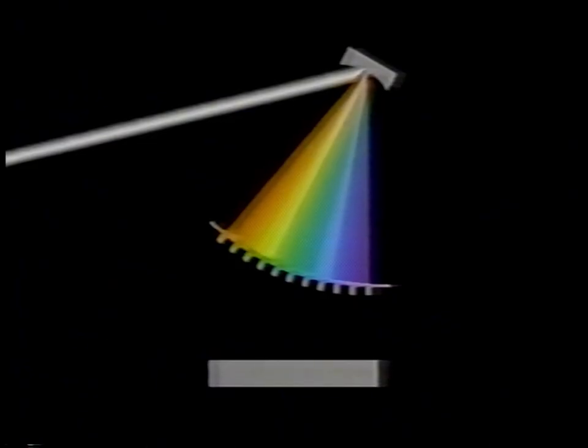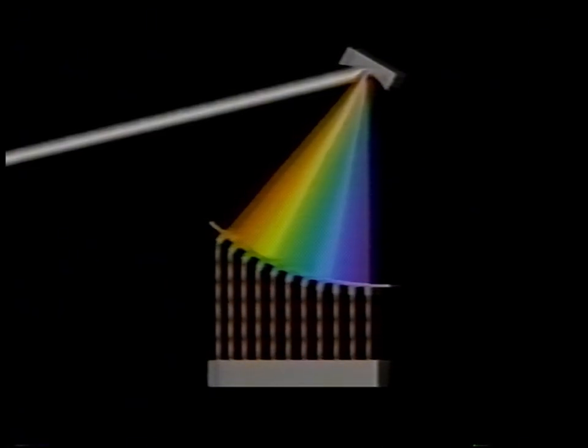A diffraction grating within the photometer diffuses the light into its component wavelengths. 12 separate photodetectors are permanently aligned to allow the use of any of 12 different wavelengths during analysis. Each photodetector converts its specific light energy into an electrical signal that is proportional to the light energy reaching the detector. The electrical signal is converted to absorbance, which is then used for the calculation of results.